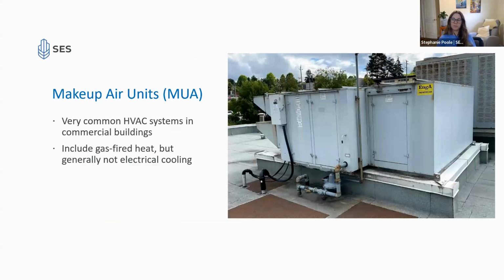Next slide. So makeup air units, I talked about this. You don't see cooling as much in makeup air units. Now, many makeup air units serve a kitchen. In that case, you'll often see cooling. So that's something to consider, if you're trying to quantify where my best opportunities are, where can I take a rooftop unit or a makeup air unit and put in a dual fuel system? The ones with cooling are going to be the easiest, right? Because you already have the electrical in there and chances are you won't need much upgrade.